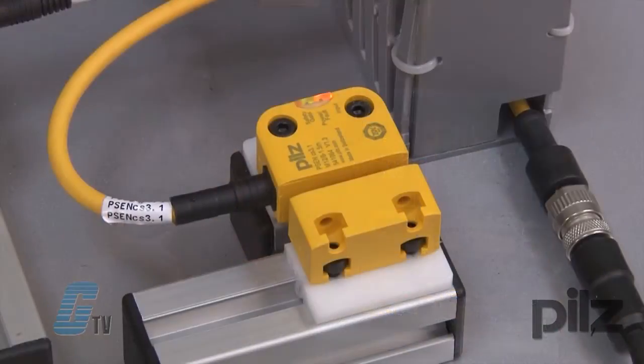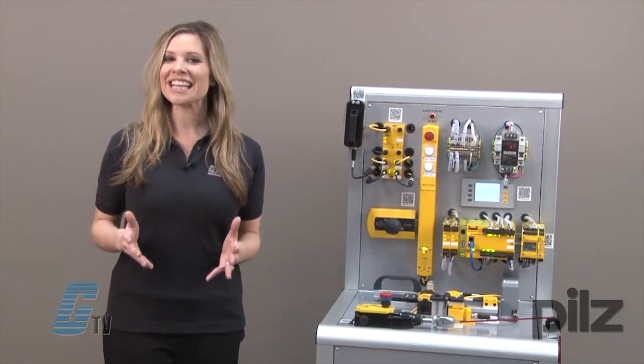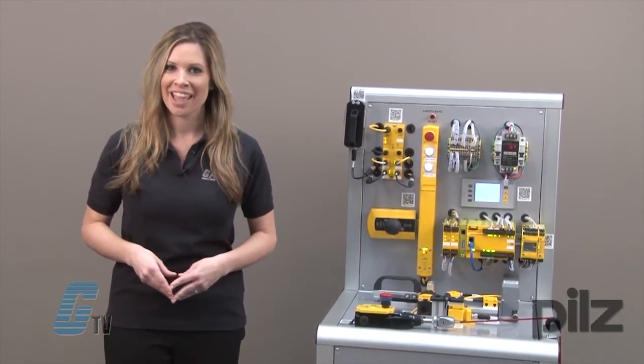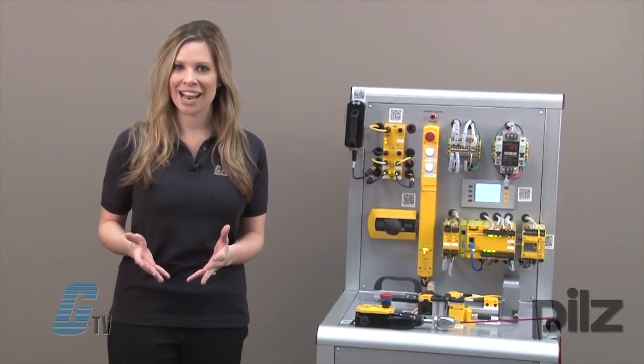My last device here is the PSENcode. They are ideal for monitoring the position of guards and simple position monitoring. These devices are housed in the same material as the PSEN MAG, thus offering IP67 protection. They offer the highest level of manipulation protection with RFID technology.